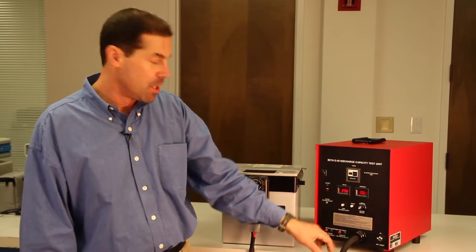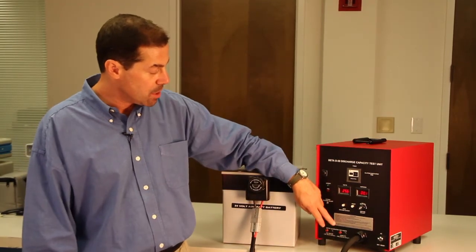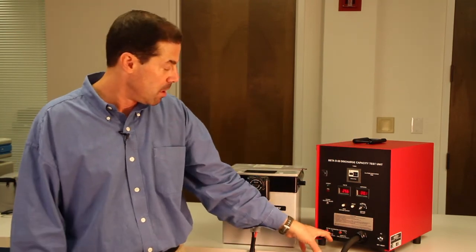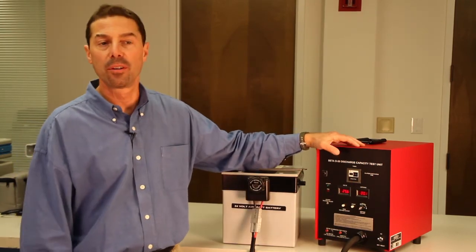The unit has calibration test points that are easy access for voltage and current. It's field verifiable if you want to measure the voltage and check the meter. If you want to check the current, you just need a good multimeter.